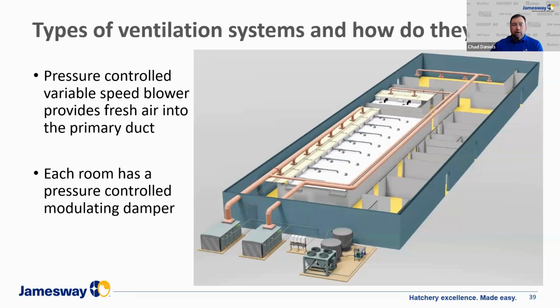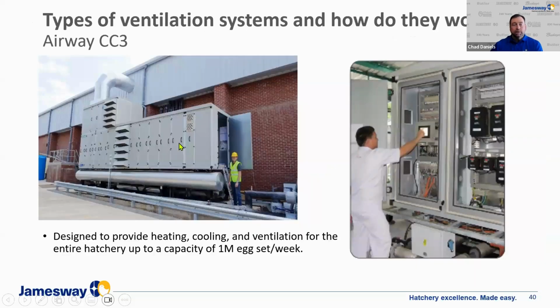So in this case, we have two. We've got one unit that's supplying pressure control to this duct, and then each room is individually controlled with a modulating damper. So we're only supplying the amount of air into that very small space that is required by the incubation equipment. And we see the same thing when we look at processing areas such as transfer rooms and chick takeoff areas.